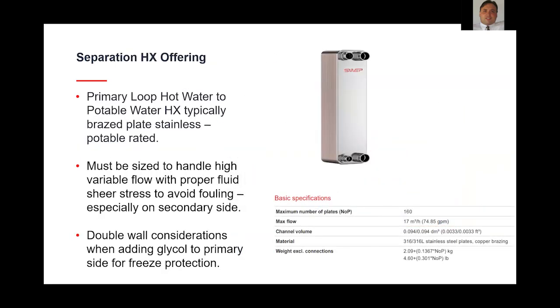Again, I mentioned the separation heat exchanger between the outdoor heat pump primary loop and then the secondary potable loop. This may vary by manufacturer. This is just an example of what Mitsubishi's partnered with through SWEP. So it's a brazed plate design.